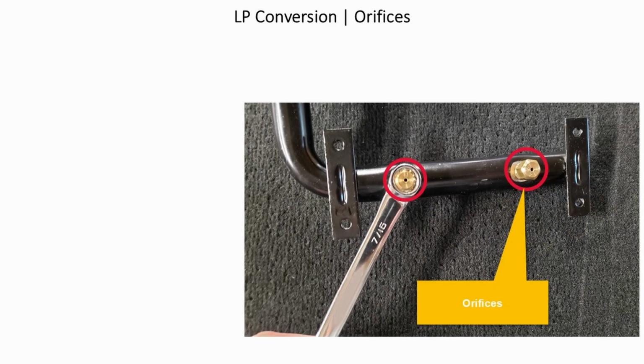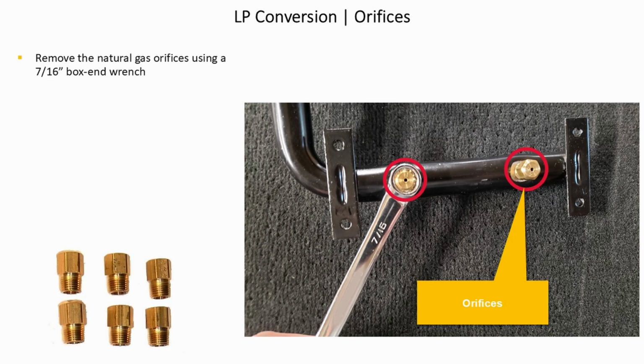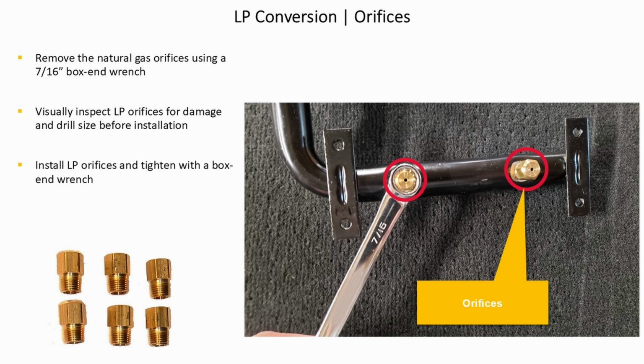LP conversions, orifices. Remove the natural gas orifices using a 7/16" box end wrench. Visually inspect LP orifices for damage and drill size before installation. Install LP orifices and tighten with a box end wrench.